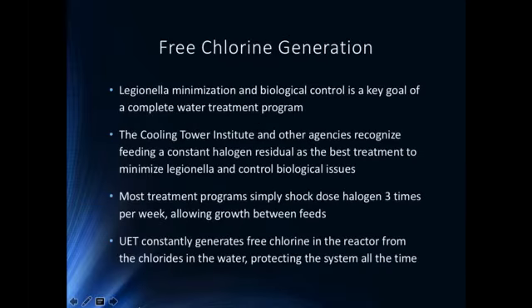So let's talk about free chlorine generation real quick. Legionella minimization and biological control is one of the key goals of a complete water treatment program. Water savings is definitely important, but we also need to keep the system clean. And the Cooling Tower Institute, ASHRAE, and other organizations recognize running a free chlorine residual at all times is the best strategy for Legionella minimization and control of biologics.